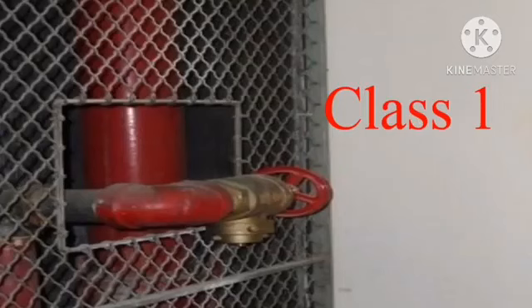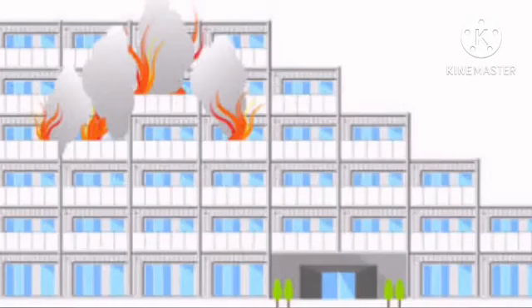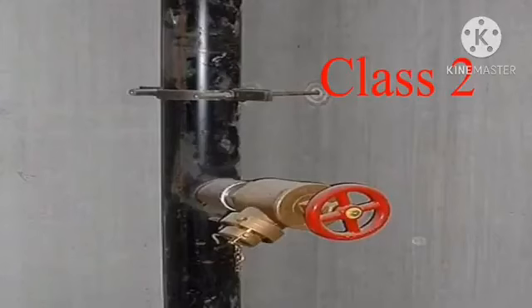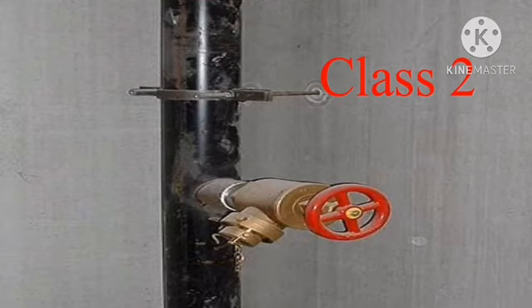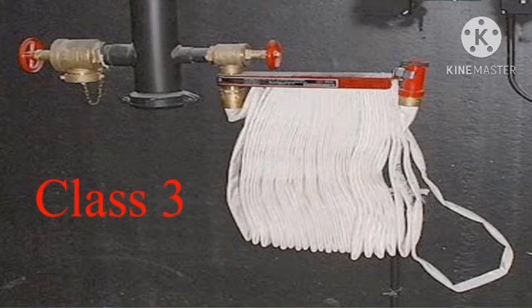There are three classes of the standpipe. Class 1 systems: 2-1/2 hose connections are provided for use by fire departments and those trained in handling heavy water streams. In high-rise buildings without sprinklers and beyond the reach of fire department ladders, Class 1 systems provide water supply for the primary means of fire fighting, i.e. manually. Class 2 systems: 1-1/2 hose lines are provided for use by trained building occupants until the fire department arrives. Class 3 systems shall provide 1-1/2 (38 mm) hose stations to supply water for use by trained building occupants and 2-1/2 (64 mm) hose connections to supply a larger volume of water for use by fire departments and those trained in handling heavy water streams.